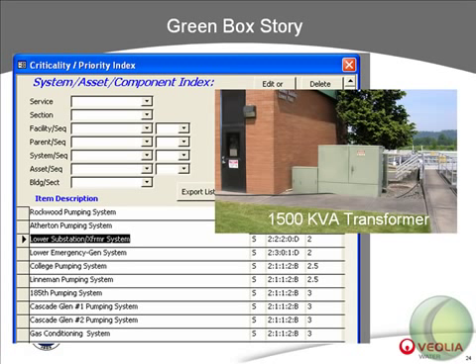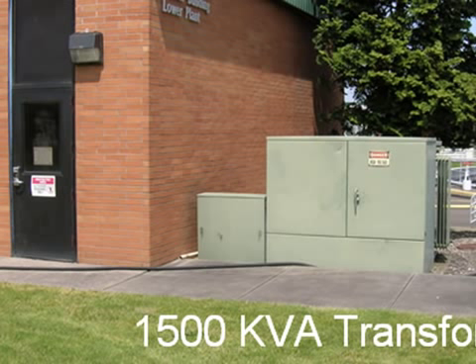There's an emergency backup generator, and the cogenerator can also feed power to this system. However, all of the power goes through a single 2,000 amp breaker, which is located just inside the door in the building. A catastrophic failure of the substation transformer could damage this breaker and leave half of the plant without power. The following short video shows just how catastrophic a transformer failure can be.